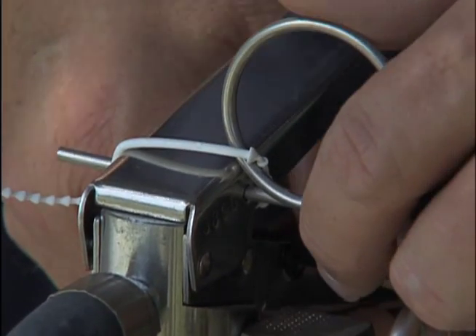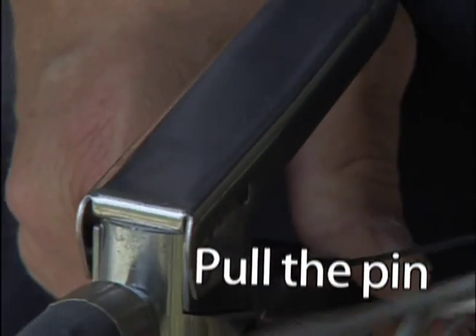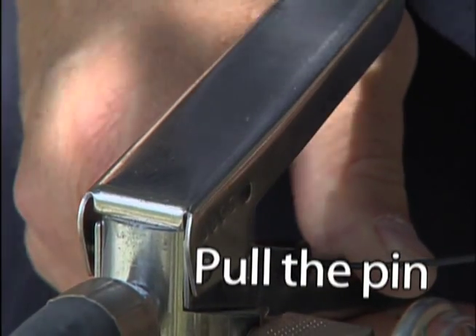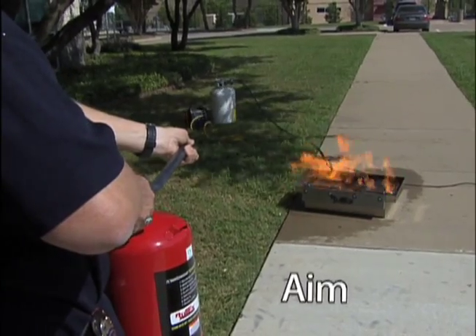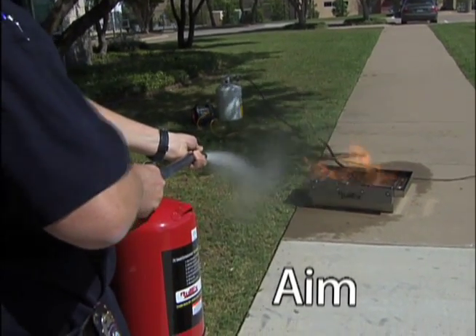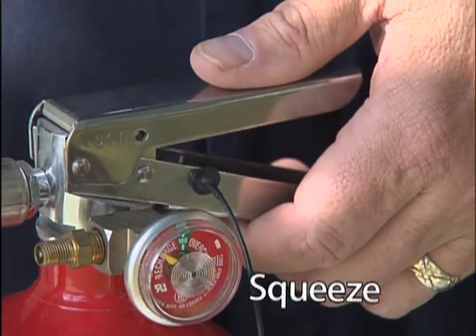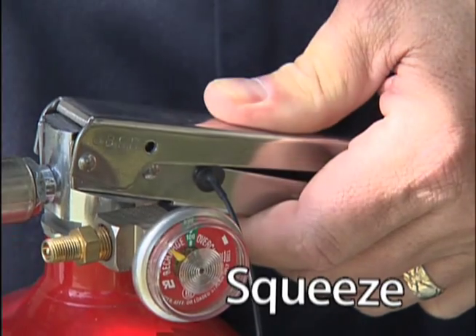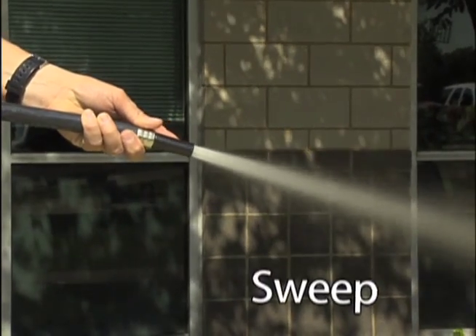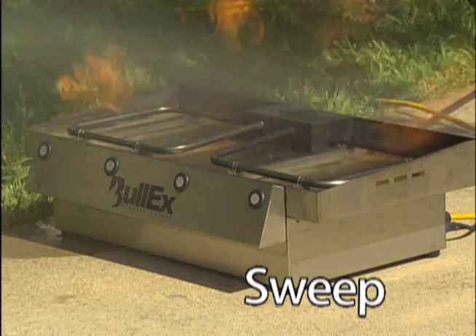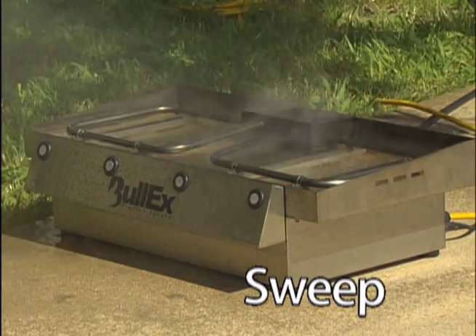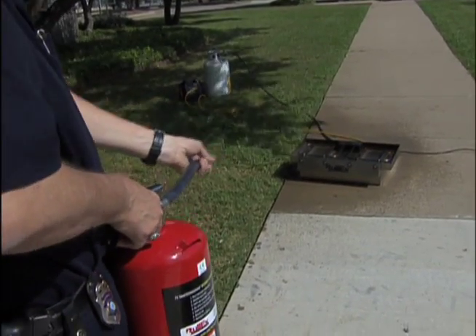The P reminds you to pull the pin. Simply turn it like a key and that will break the seal that holds the pin in place. A reminds you to aim at the base of the flames where the fuel is. The first S is squeeze the levers together fully. The second S reminds you to sweep the base of the flames. Even if you put the fire out, keep an eye on it in case it flares back up again.